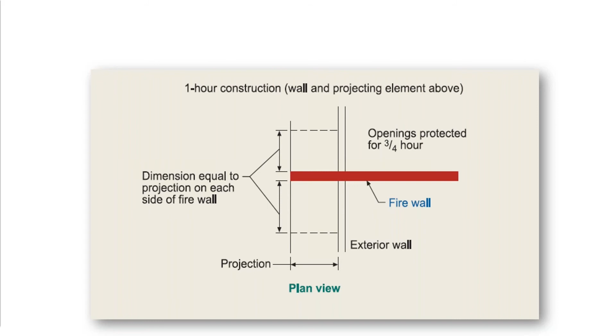And then for the other exceptions with the concealed spaces or no concealed spaces, on the left you've got the one that doesn't have a concealed space but it has a projection, and you've got the firewall. What happens there? You've got to have a 1 hour. Shows you how to terminate with a 1 hour, when the exterior is 1 hour and the same openings are protected for 3/4 hour. And then what if you do have a concealed space? That firewall goes all the way through.